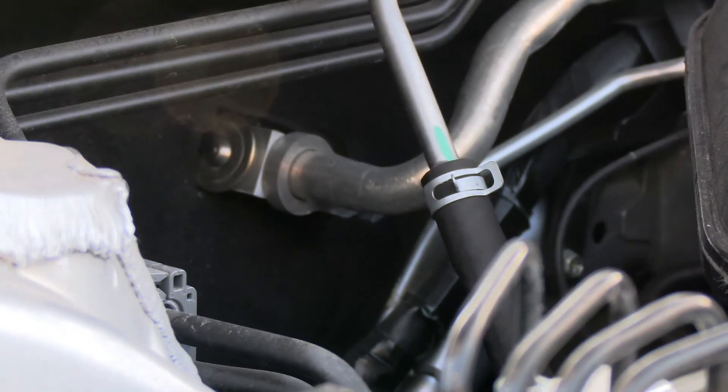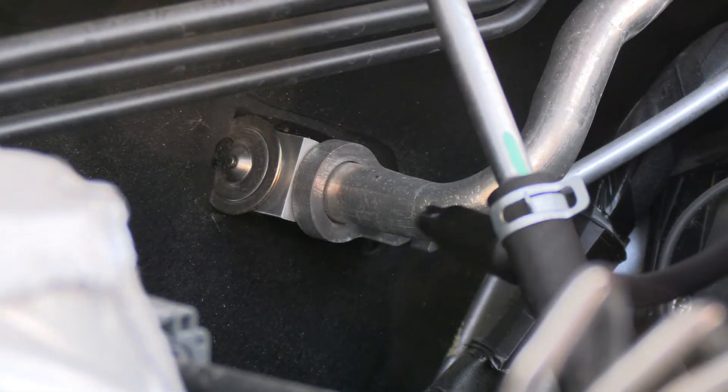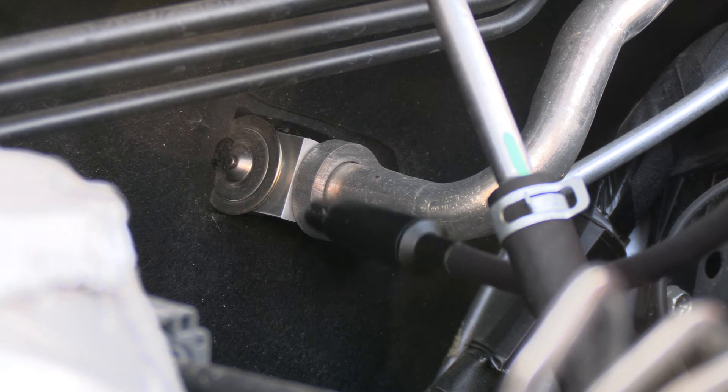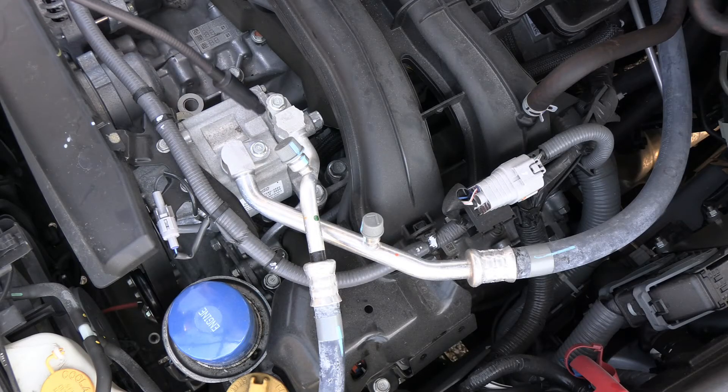Place the tip of AST 200 IR as close as possible to the suspected leak. Be careful not to block the airflow as this can cause false alarms. Slowly move the probe past each possible leak point.